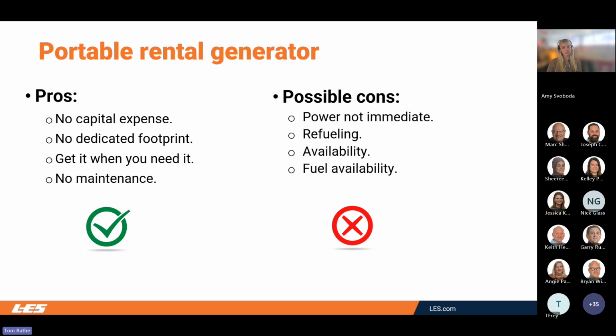But there are also some possible cons: how long is it going to take to get one in place, connected, and in operation when you need it? Is that going to be fast enough? Best case, this is going to take a few hours, maybe closer to a full day in a worst case scenario. Are you going to be able to refuel it? It's going to take more than a 5-gallon gas can—these are pretty large units. A portable bulk tank or bulk delivery is going to be required fairly frequently. Most portables will be gas or diesel, again requiring large quantities of fuel. For example, a 500 kW generator can burn in excess of 50 gallons of fuel an hour, so that refueling plan is a major consideration if they're running pretty heavily loaded.